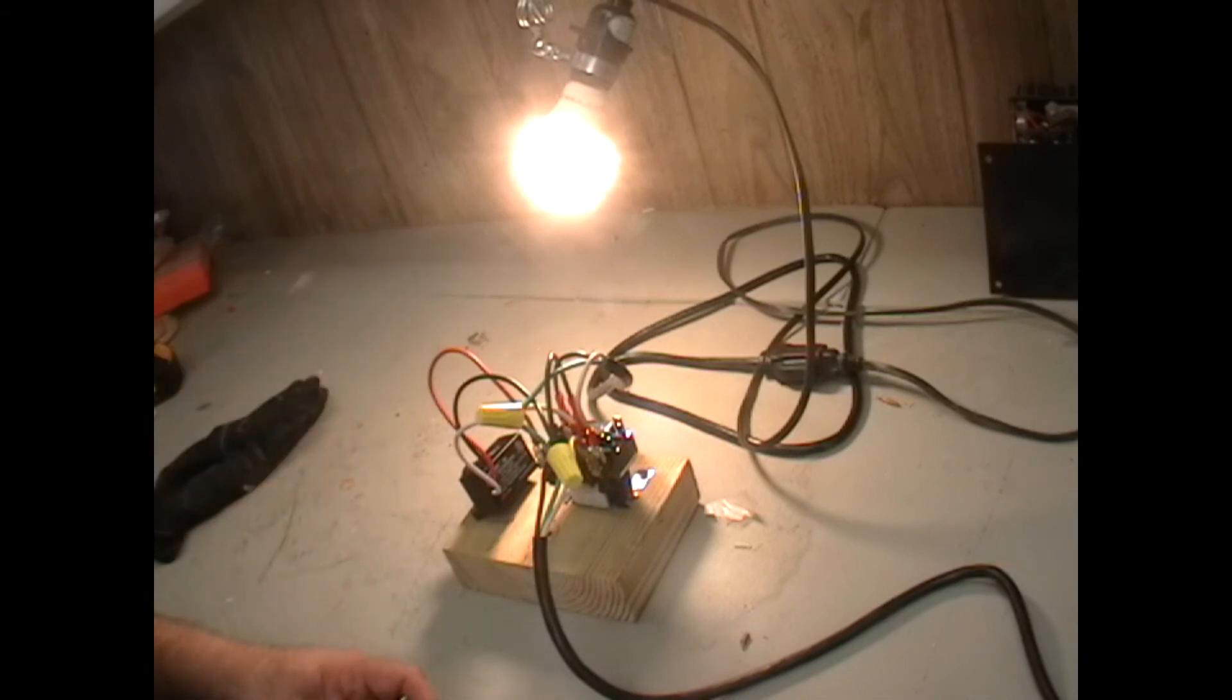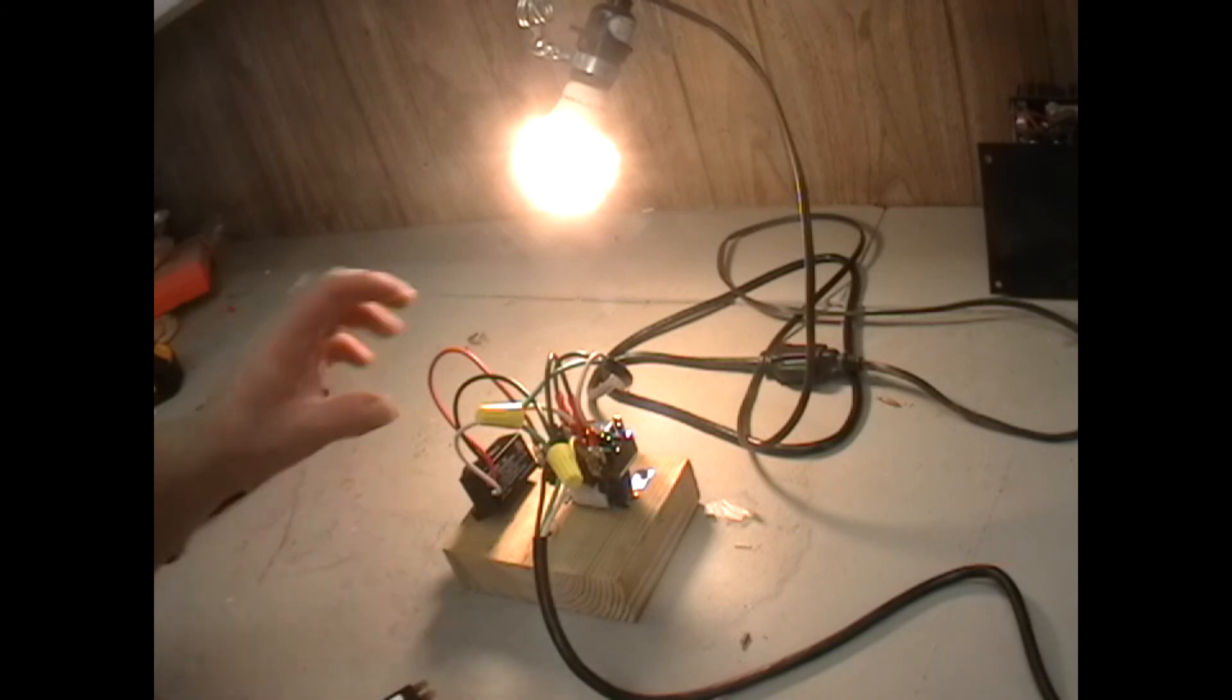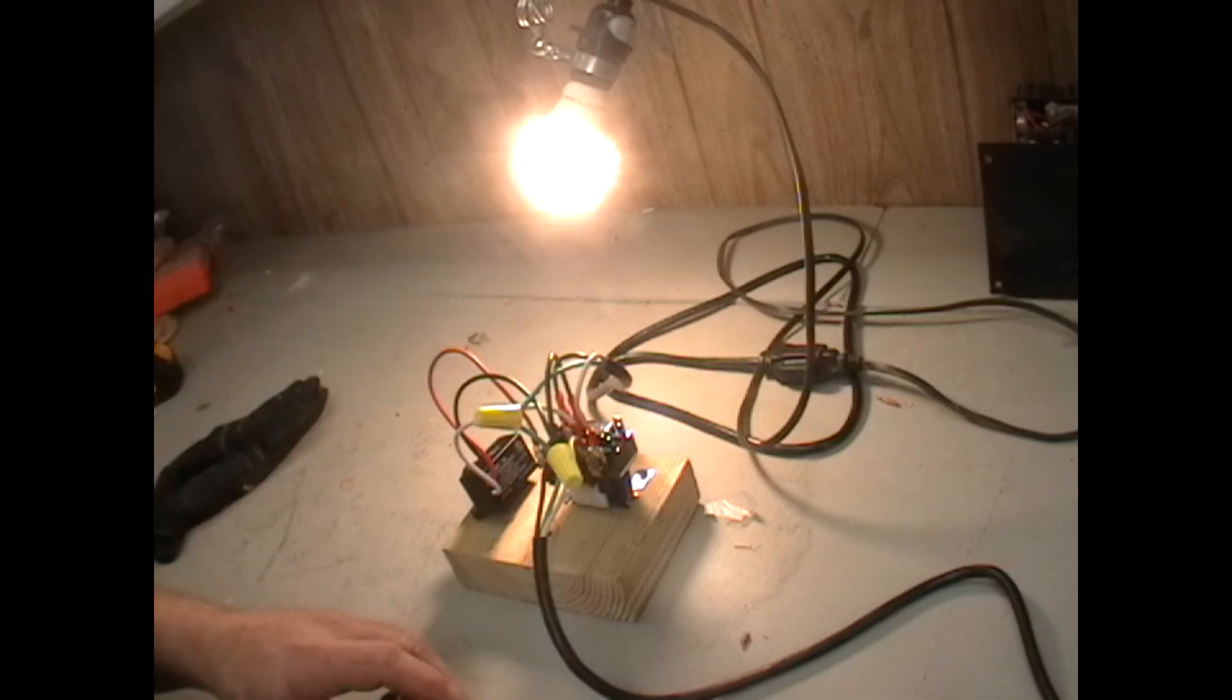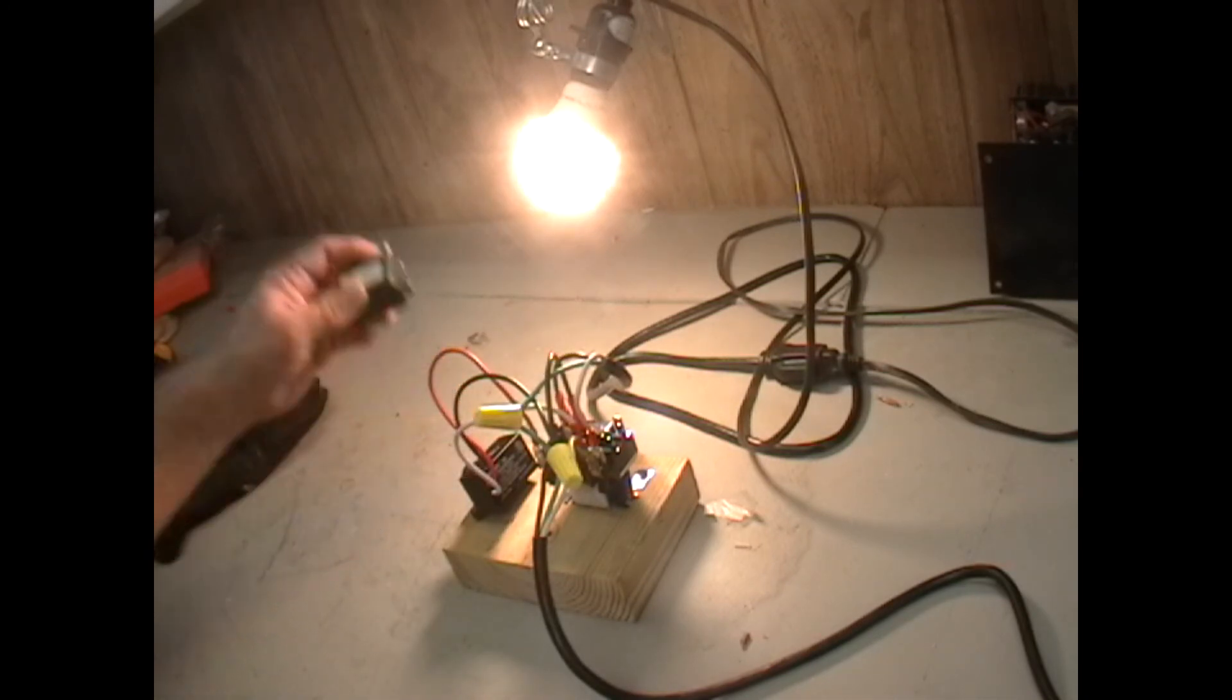So what you could do is use the relay to, like instead of powering this light, you could hook a 120 volt contactor down line from this relay. So this would just power a contactor instead that could carry 30, 40 amps if you needed to do a bigger job with it.